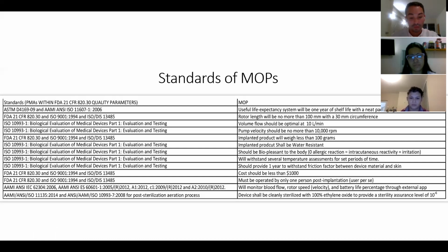On the other hand, the ISO, which I already mentioned as the International Organization for Standardization, also has another parameter, numbered 10993-1, also named Biological Evaluation of Medical Devices, specifically Part 1, which is called Evaluation and Testing. These will also be evaluated for volume flow, pump velocity, which will not be more than 10,000 revolutions per minute, as well as water resistance, which will be evaluated in pressure points, such as atmosphere levels or meters below water level, as well as other factors, such as biocompatibility with the body, which covers allergic reaction, intracutaneous reactivity, or the irritation produced by the implantability of that device.